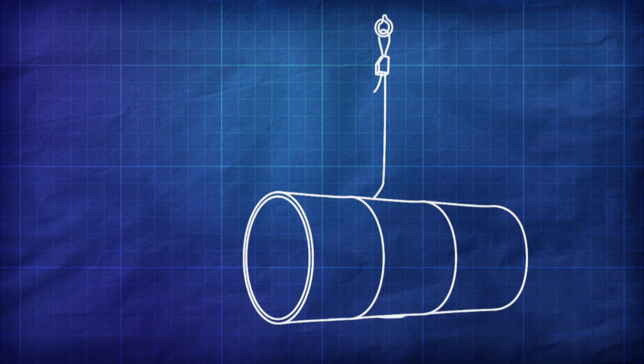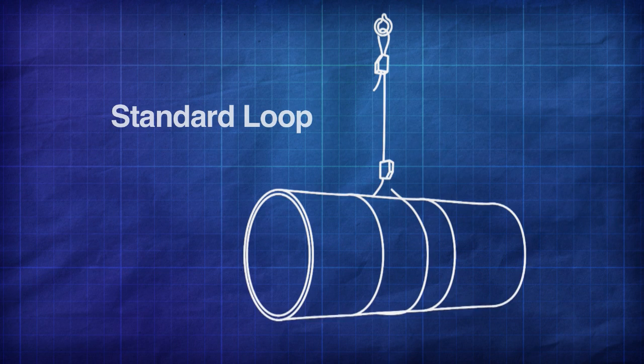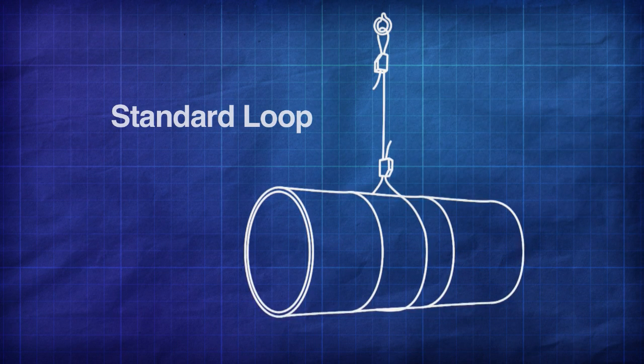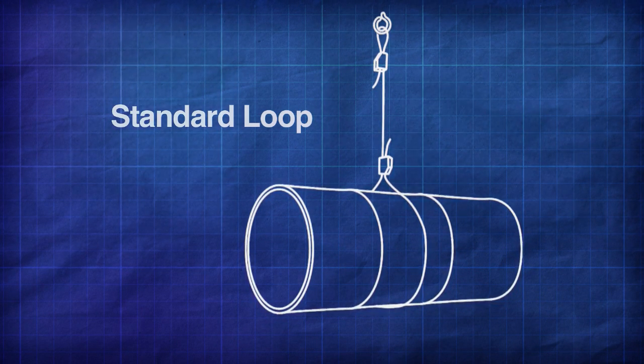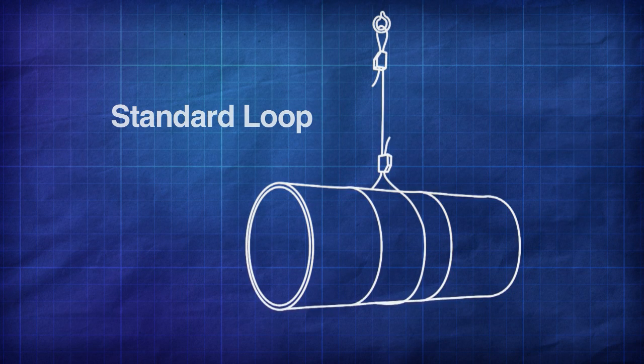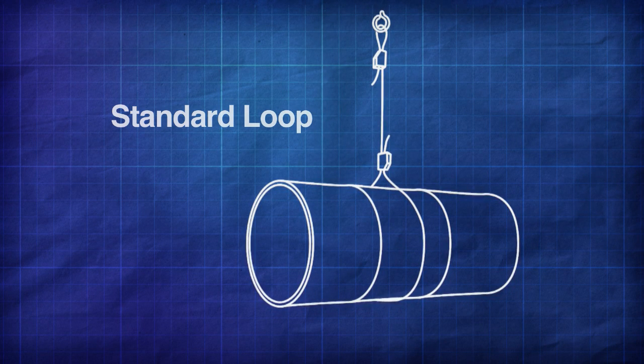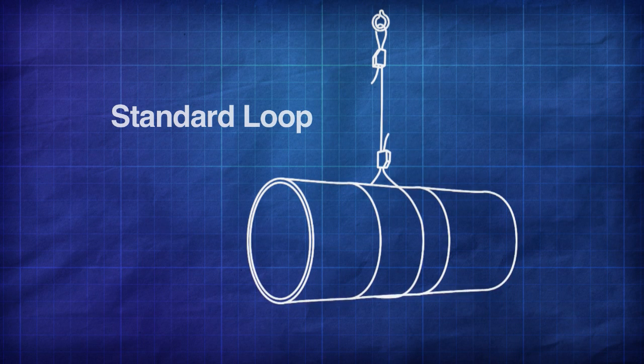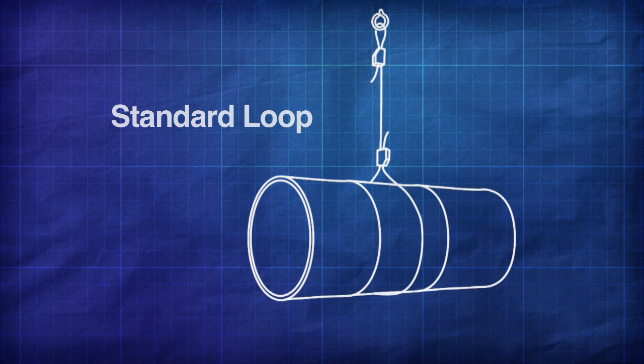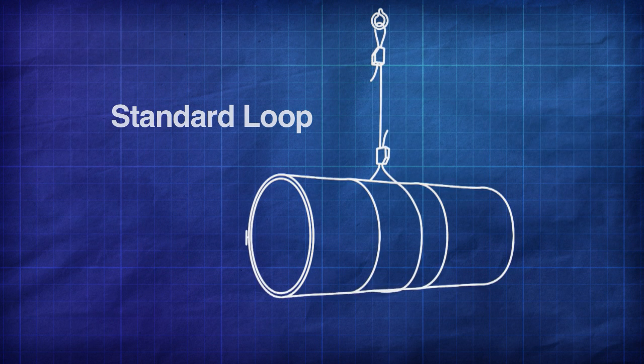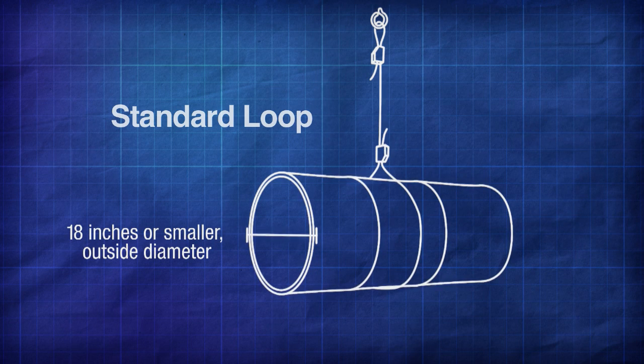The final configuration is the standard loop. The steel cable is looped around the upper support and secured with a clutcher mechanism, then looped around the duct and secured with another clutcher mechanism. The standard loop configuration is suitable for applications where the duct will not experience lateral forces or be prone to swinging. The advantage of this method is its simplicity. This configuration can be used for general-purpose hanging and is recommended for duct diameters up to and including 18 inches.